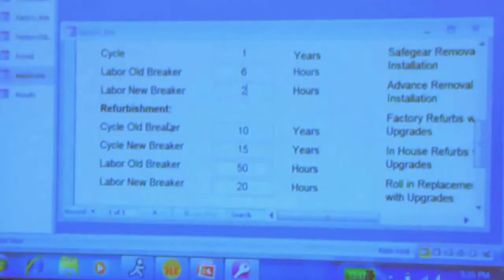Refurbishment - how often do you fully refurbish your breakers? Never? Okay, I'm not allowed to put 0 in here because there's a lot of math in the spreadsheet. So I'll put in how old the gear is - 30 years old? Let me just say 30 instead of 0, because if you try to divide something in an Excel spreadsheet by 0, it'll give me a default and flag that I can't put 0 in there. On the new breaker, the vendor recommends a cycle of once every 15 years.